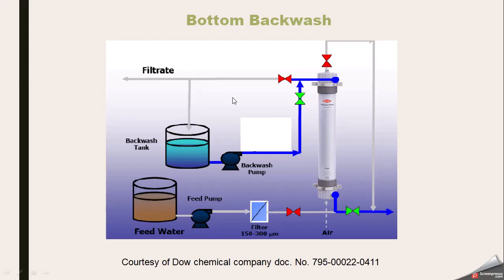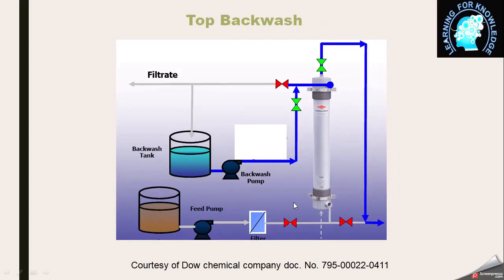In bottom backwash, the pump takes water from the backwash tank; water enters from the top, the top valve is closed, and cleaning water exits from the bottom. In top backwash, water enters the module through the inside of the membrane, goes outward, and exits from the top carrying dirt and cleaning material.